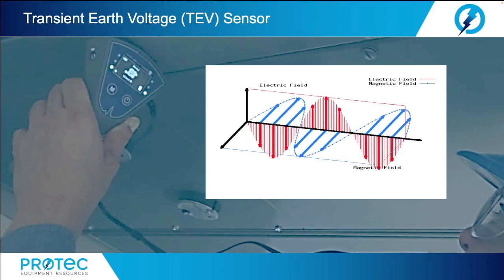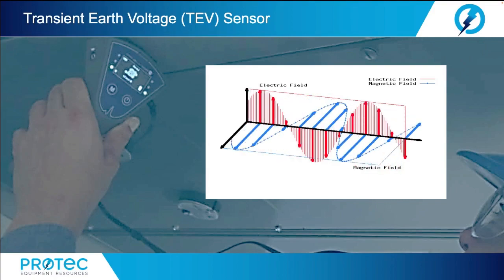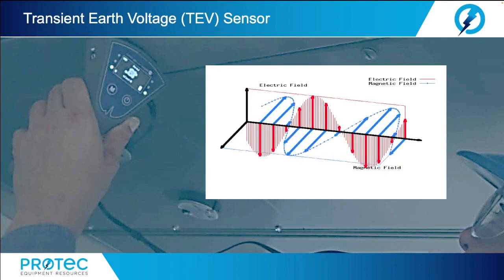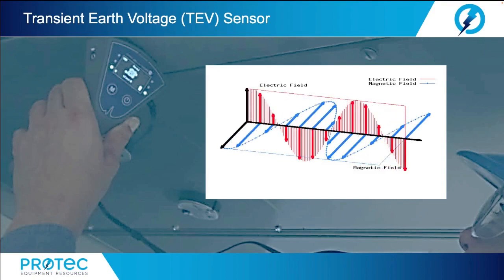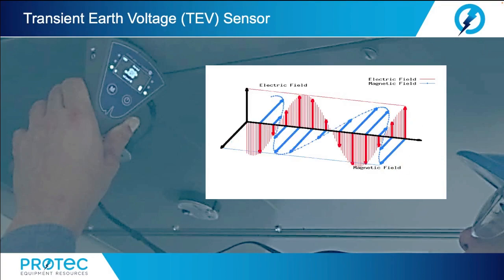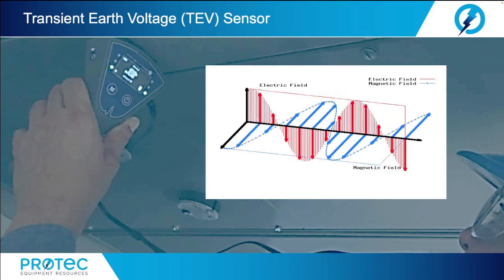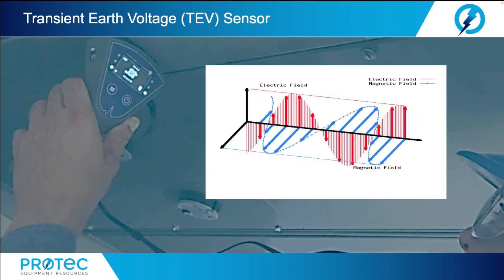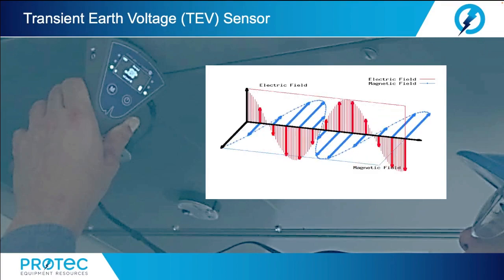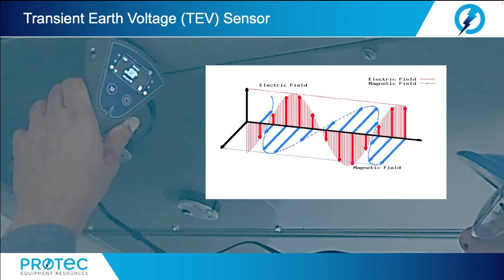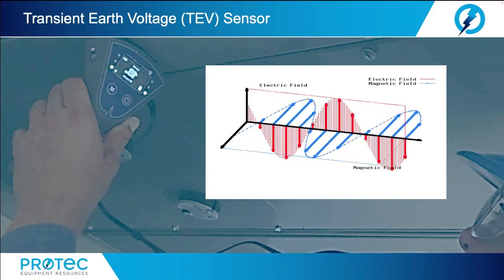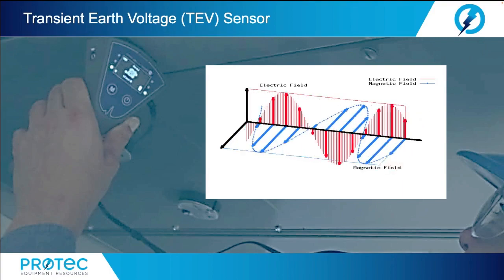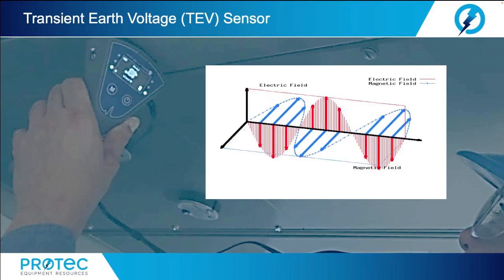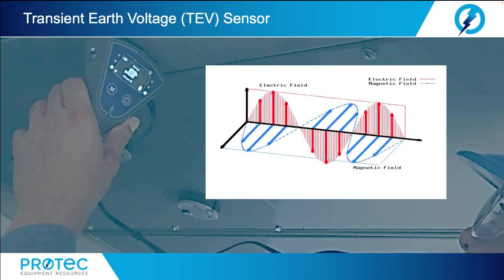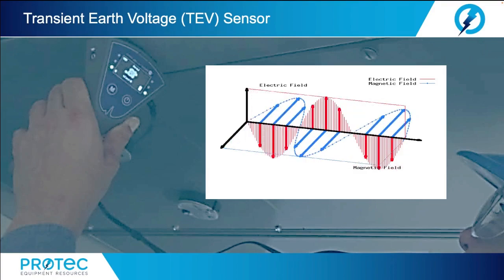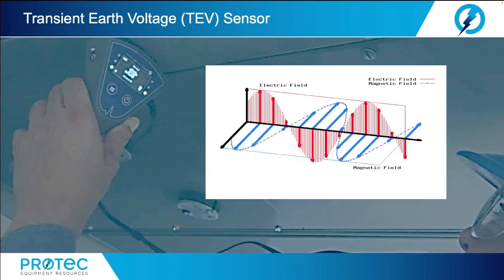PD from overhead can induce a TEV signal on an entire line of switchgear. The TEV sensor is a type of capacitive coupler which is built into the main PD detection unit. The TEV sensor is reliable for indicating most types of PD in metal clad switchgear, but it also responds to noise from lighting systems, battery chargers, variable frequency drives, LEDs, and large motors.